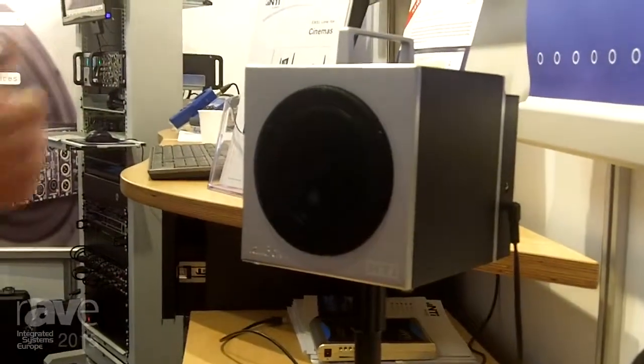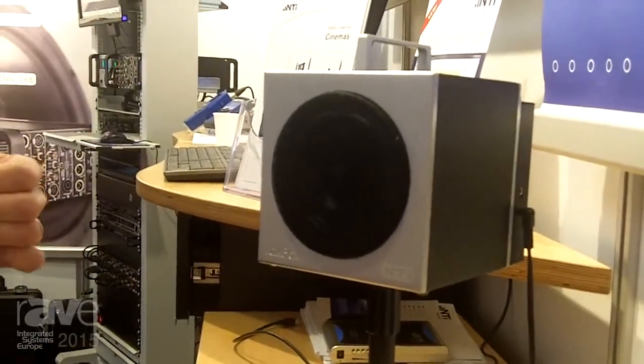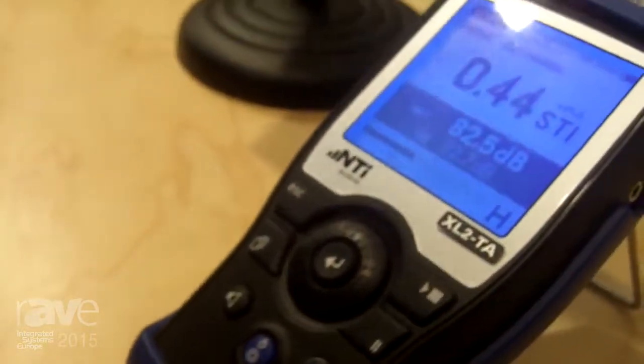This test signal is inserted into the room via the voice mic, and the instrument measures the speech intelligibility and gives you immediately the reading of the speech transmission index, giving you all the information, what's going on and what's the quality of the audio system.